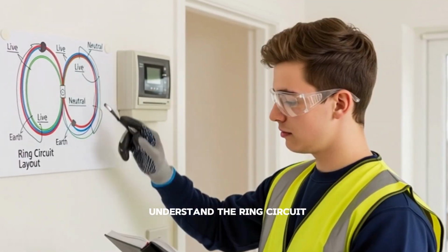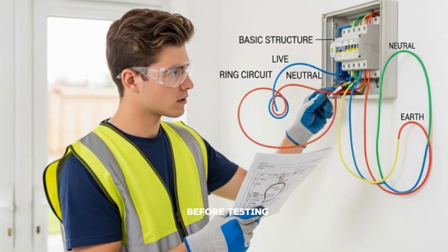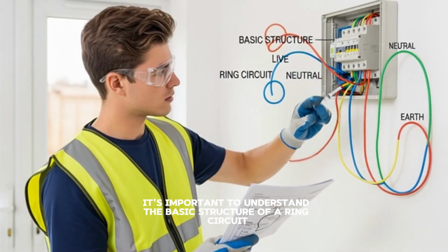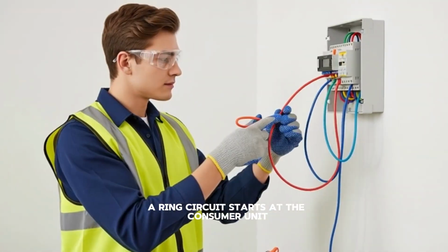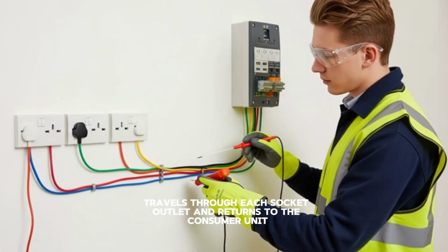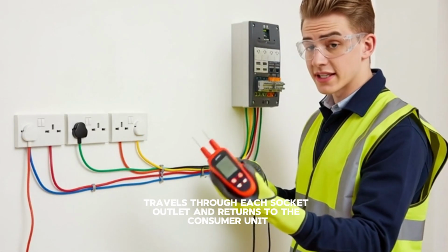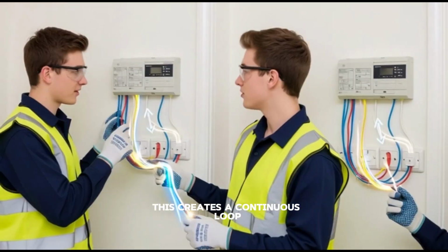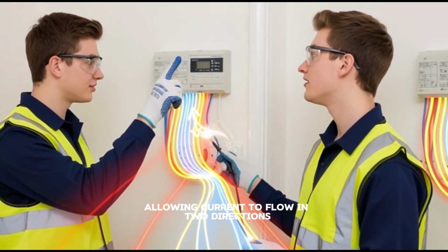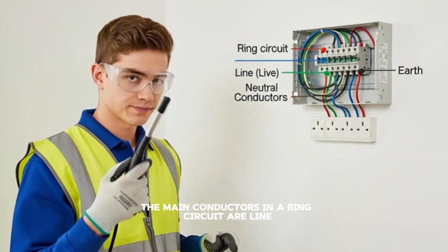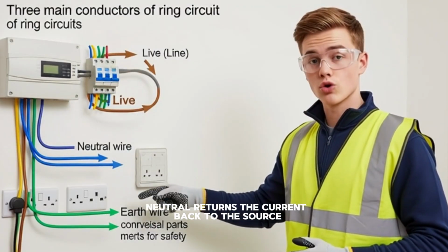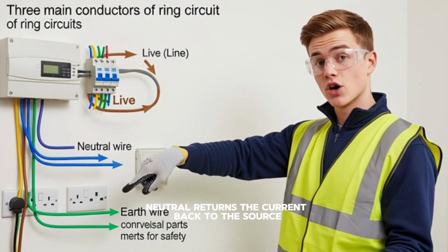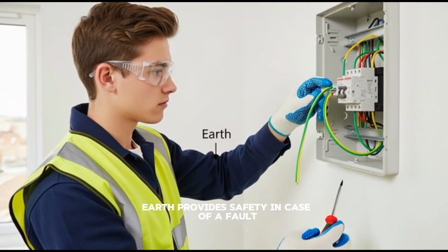Step 1. Understand the ring circuit. Before testing, it's important to understand the basic structure of a ring circuit. A ring circuit starts at the consumer unit, travels through each socket outlet, and returns to the consumer unit. This creates a continuous loop, allowing current to flow in two directions. The main conductors in a ring circuit are: line, or live, which carries the current to appliances; neutral, which returns the current back to the source; and earth, which provides safety in case of a fault.